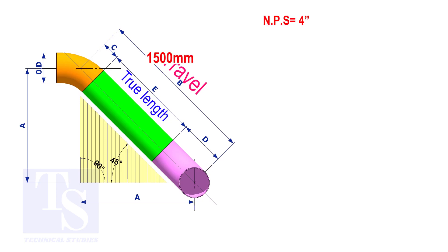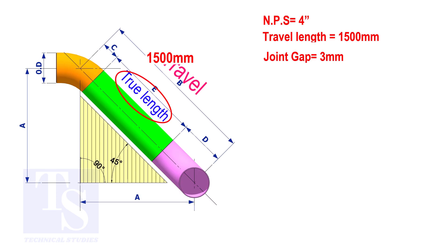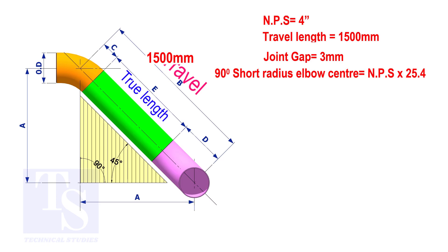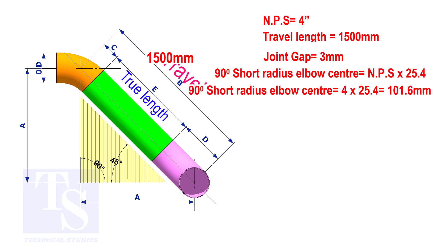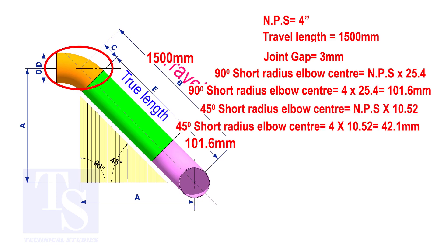Nominal pipe size is 4 inch. The travel length is 1,500 millimeters and the joint gap is 3 millimeters. To calculate the elbow center of a 90 degree short radius elbow, multiply the nominal pipe size by 25.4. The answer is 101.6 millimeters. To calculate the elbow center of a 45 degree short radius elbow, multiply the nominal pipe size by 10.52. The answer is 42.1 millimeters.